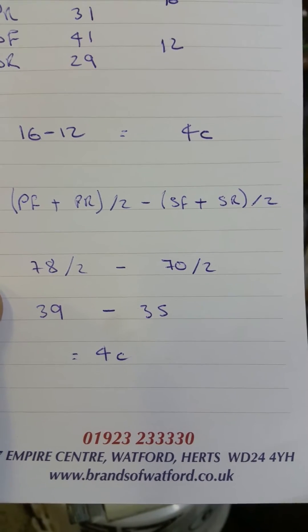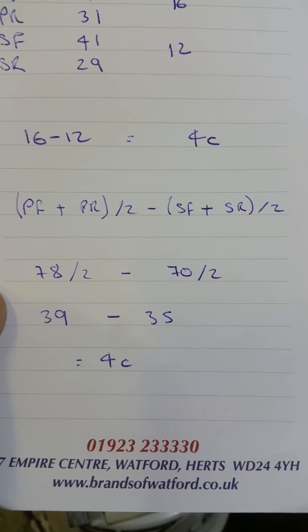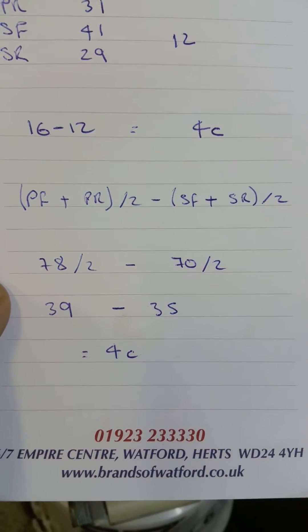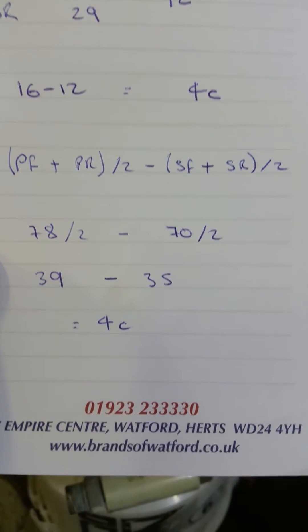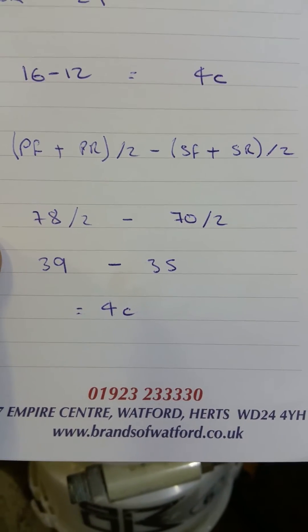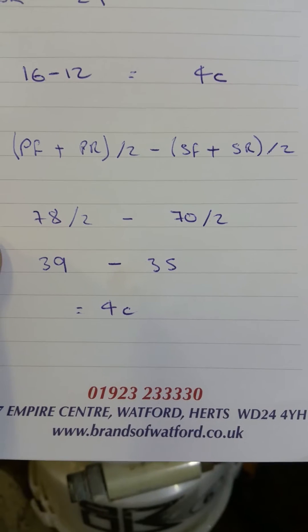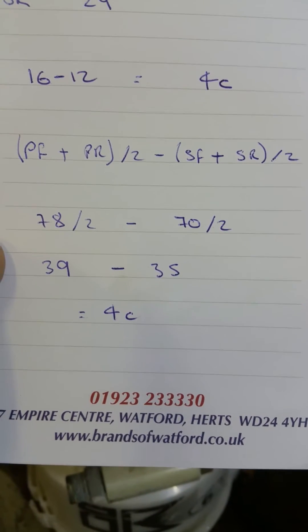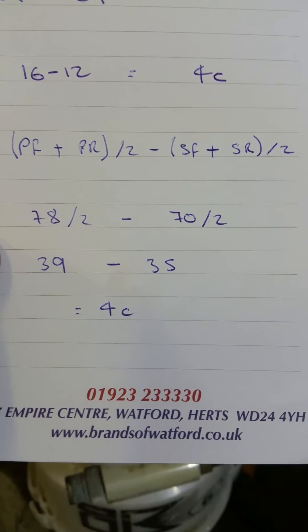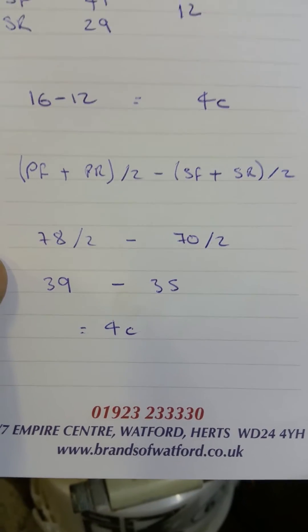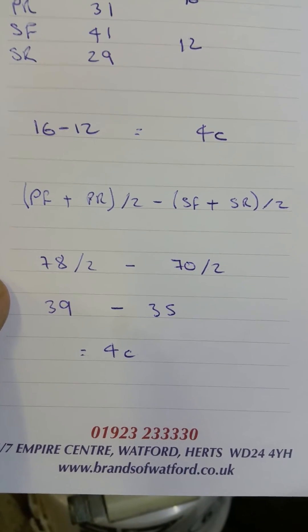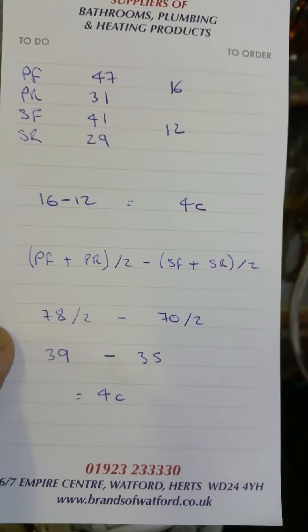Applying numbers to that formula and working out both sides gives 78 divided by 2 minus 70 divided by 2, which is 39 minus 35, and that does give us the same answer of 4 degrees. This is at full load — it's not running at full load right now.